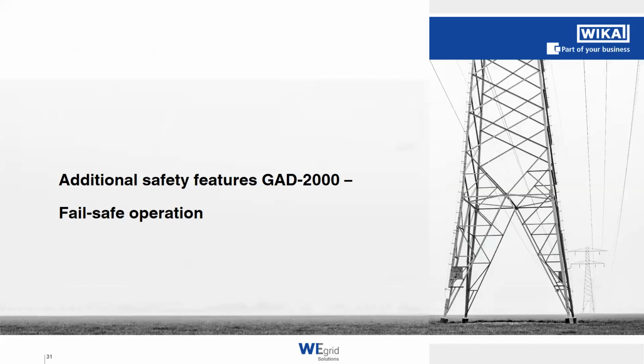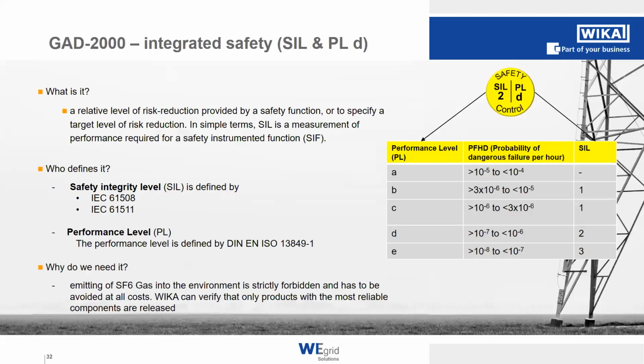Since the GAD 2000 is working online with the GIS in operation, we have to make completely sure that the operation is fail-safe. Therefore, we integrated components which work at the highest level of reliability and are certified with the SIL and the PLD sign. What does SIL stand for? It's called Safety Integrity Level, and it's defined by the two IEC norms you can see written in the text here. When you reach a certain safety integrity level, this also gives a performance level, which is defined by DIN and ISO norms as well.